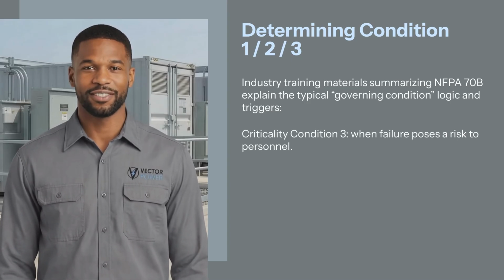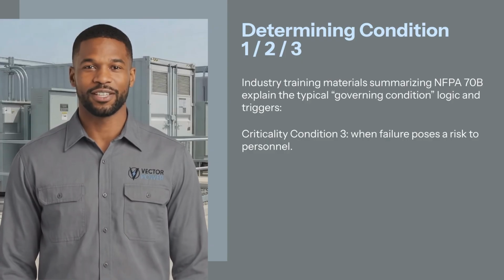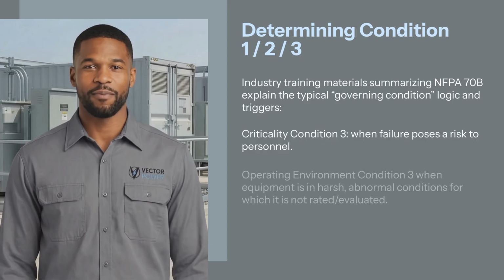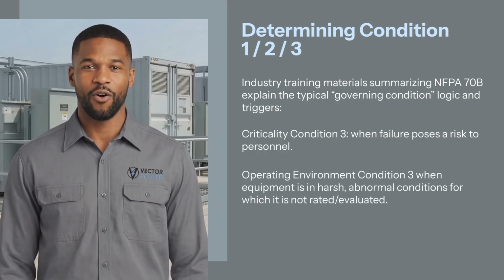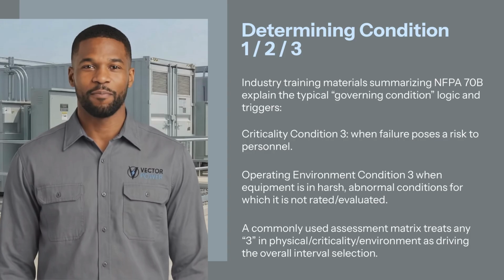Criticality condition 3, when failure poses a risk to personnel. Operating environment condition 3, when equipment is in harsh, abnormal conditions for which it is not rated and evaluated. A commonly used assessment matrix treats any 3 in physical, criticality, or environment as driving the overall interval selection.